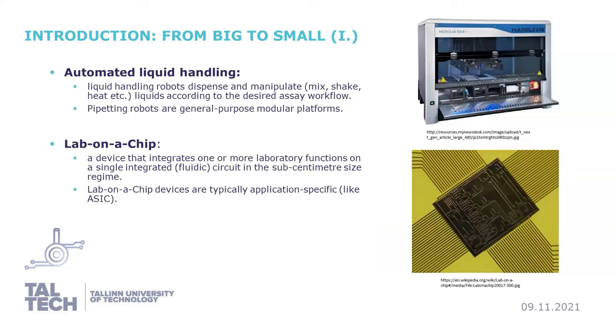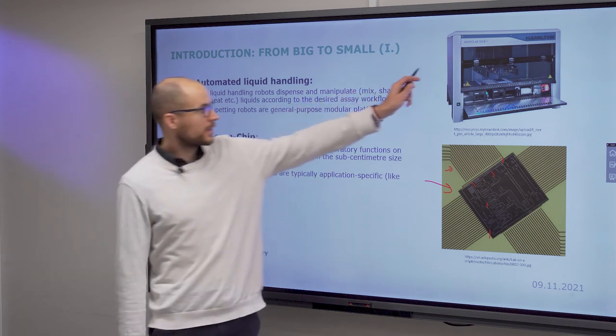The standard solution would be to use multi-channel pipetting in robots with air displacement pipets. The alternative would be to use lab on a chip type devices, where different functionalities are unified on a single die with various fluidic channels, connections, and electronic interfaces for sensors and actuators. Here is a close-up view of the Hamilton Star robot, one of the popular industrial liquid handling robots, which has several channels of air displacement pipets that move on a three-axis robotic arm and can pipet from container to container based on your workflow.